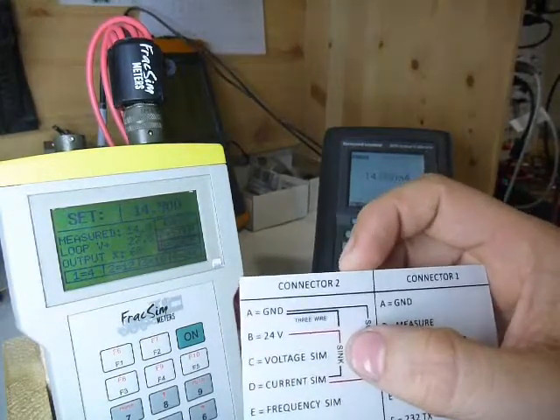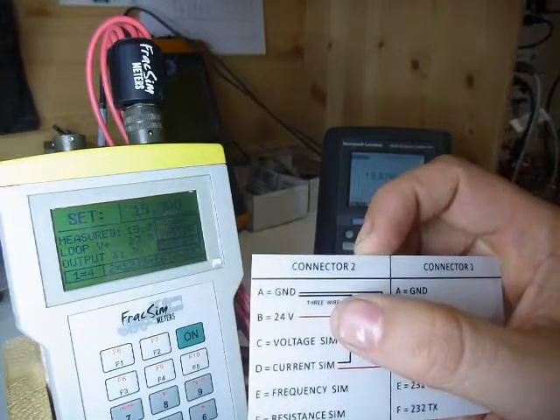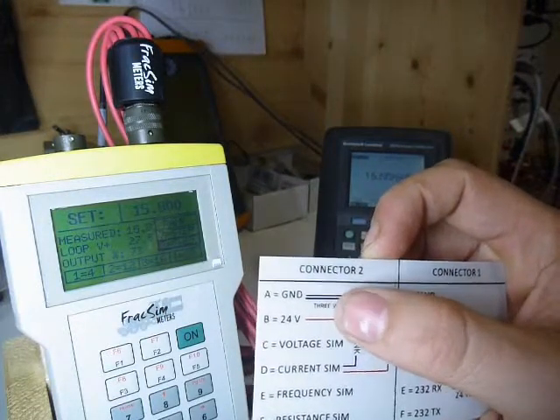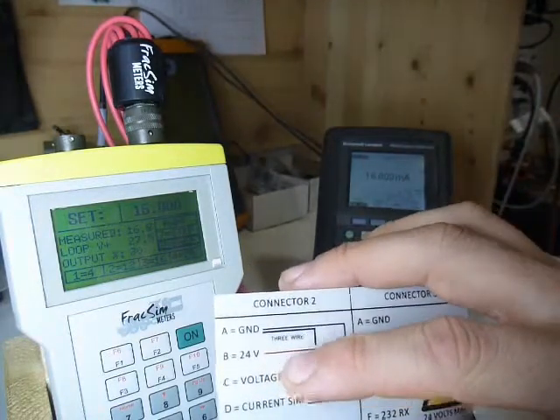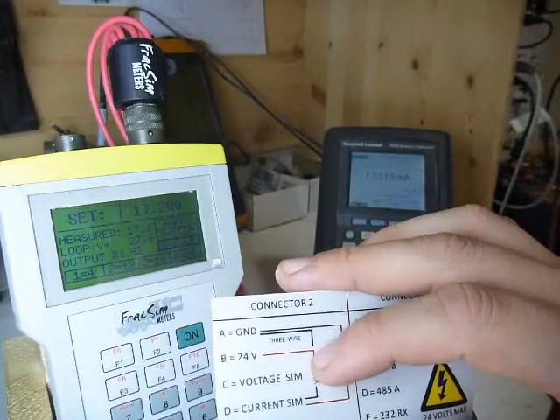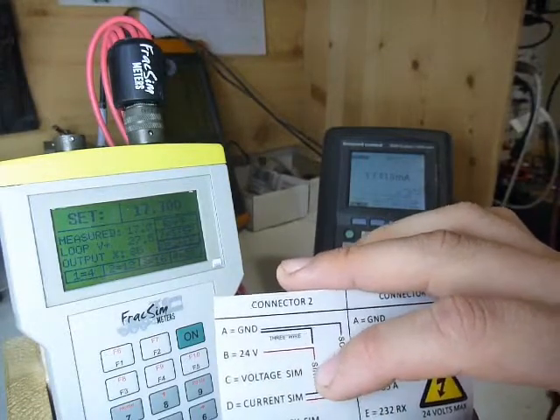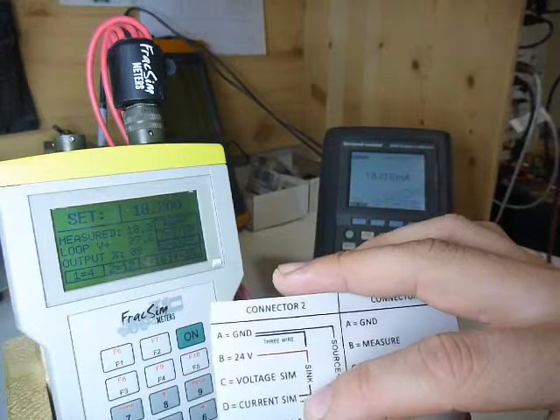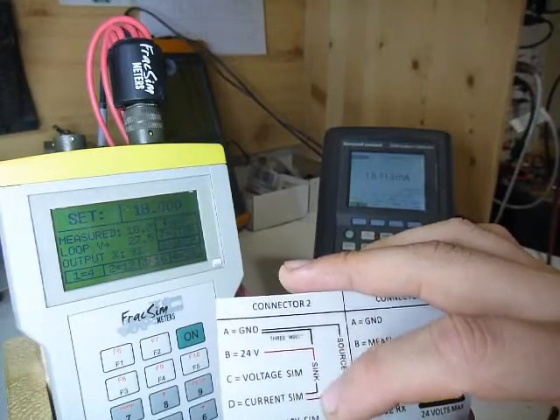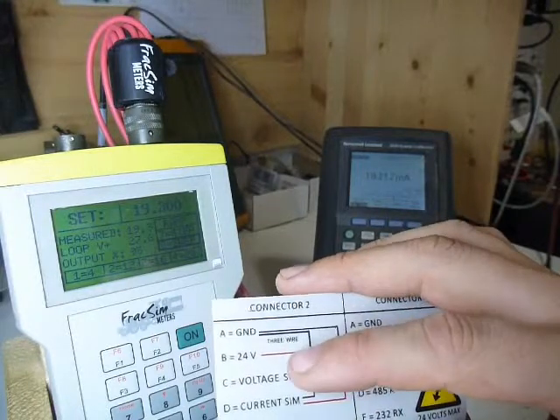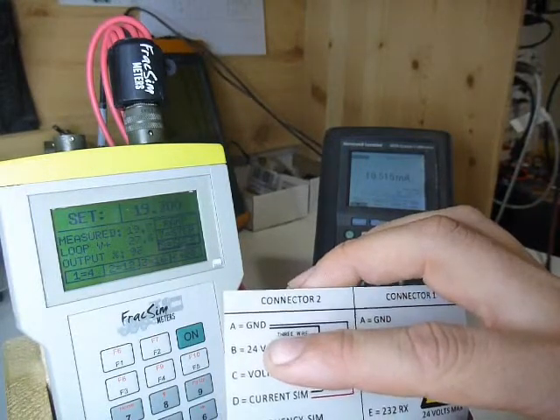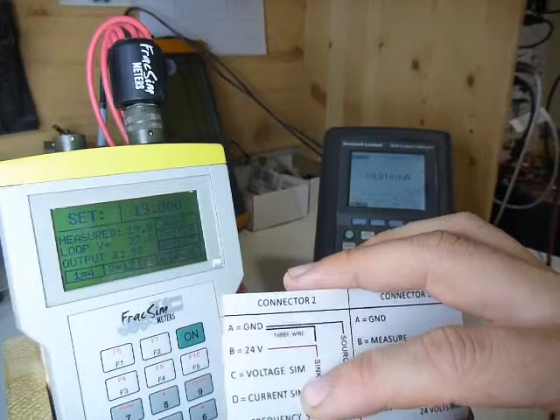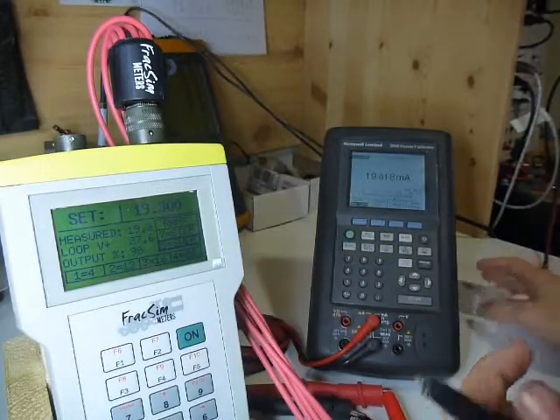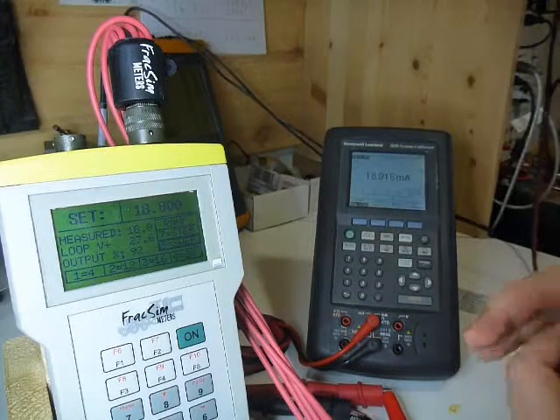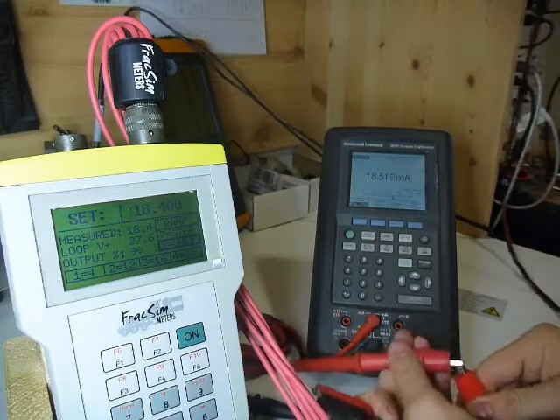So where it says sinking current, you've got 24 volts there. You're going to hook up 24 volts onto where it says 24 volts, that'd be from the unit. Again, red is from the unit, positive, and then the black is the return. So instead of going from the current sim to ground, we're going from the unit into the 24 volts and then back out on current sim. So we're going to pretend 24 volts from the power supply is from the unit.